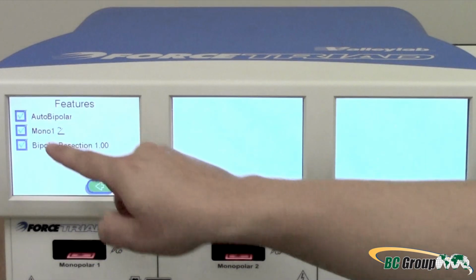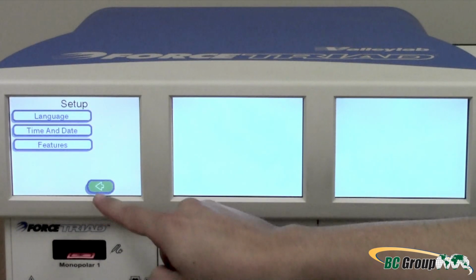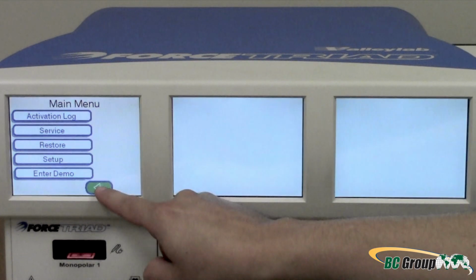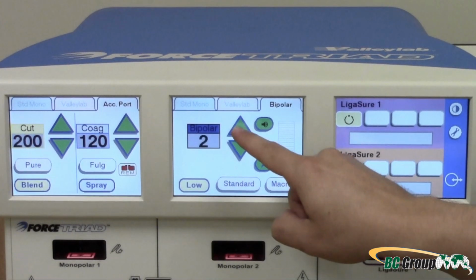Make sure the autobipolar option is checked. Return to the main screen by pressing the green back arrows. When the system is in autobipolar mode, a green button labeled A appears in the middle window of the generator. Set the bipolar power to 20 watts.